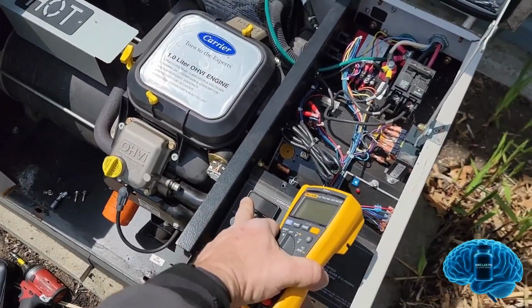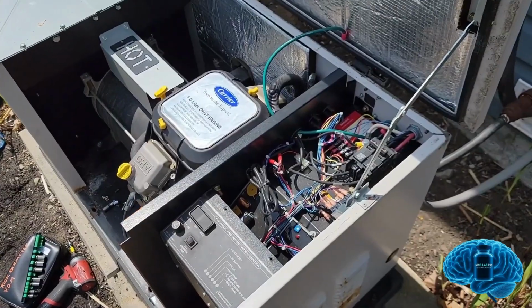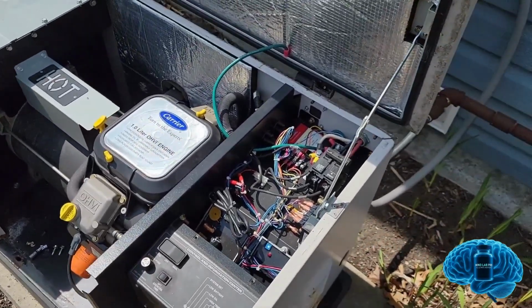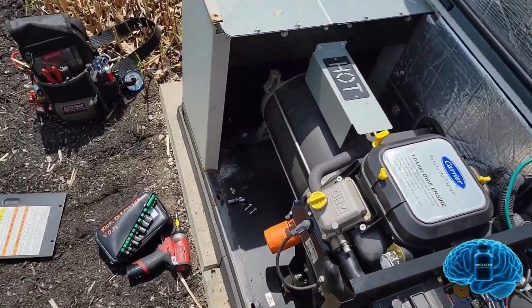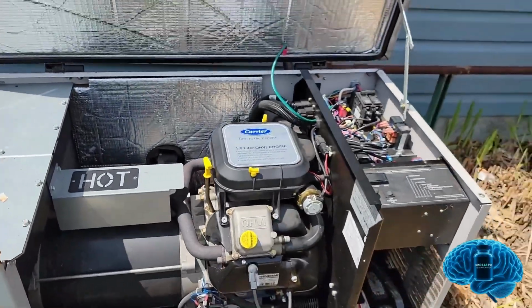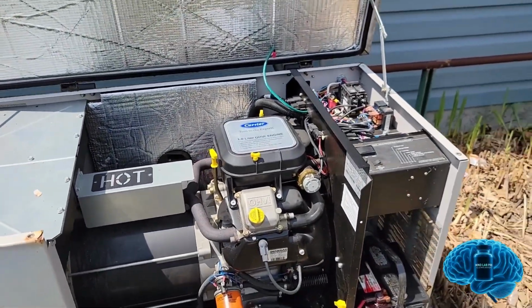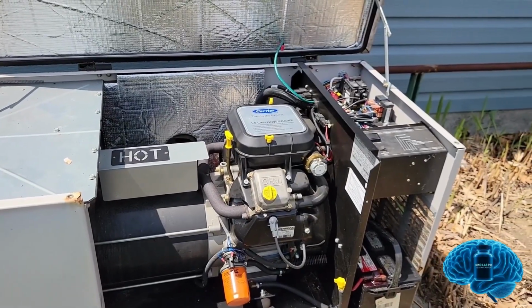So voltage and stuff is fine. The only thing left to do now is test the transfer switch to make sure it's actually going to transfer over. It doesn't do them a whole lot of good to have a generator running if it doesn't transfer over, and unfortunately, that's one of the most important tests at the end there you need to be doing.